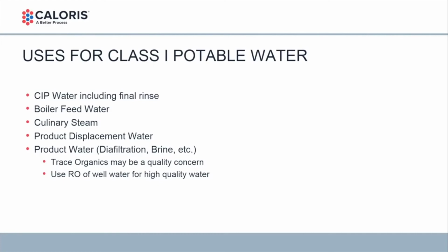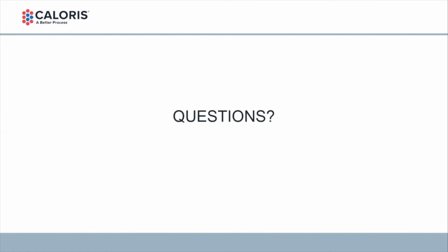The only issue is, again, you have to be aware there could be trace organics, and they could be a quality concern, getting into your product. And if that is a concern, you don't want that in your product, and you don't want the high TDS in your product from regular city water, then I'd suggest using well water for your RO source, and that'll give you the best quality water. And with that, I'll take any questions at this time.